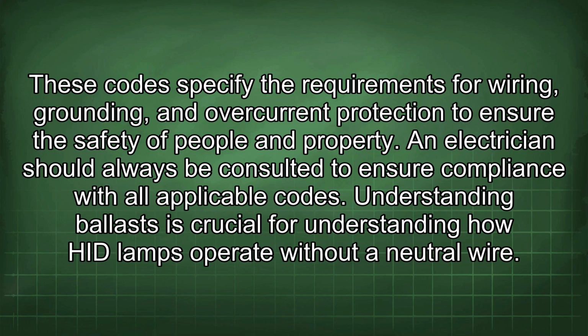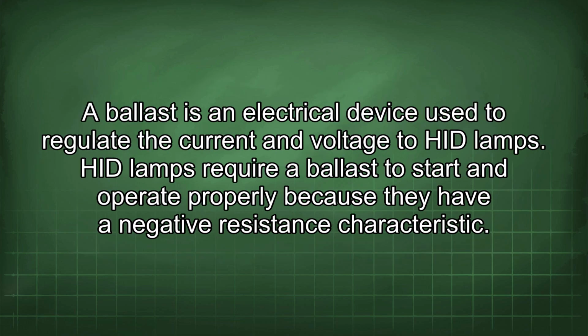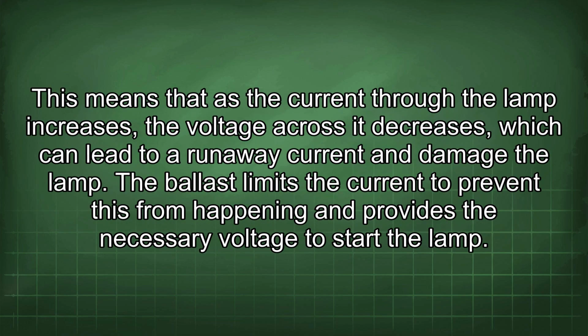Understanding ballast is crucial for understanding how HID lamps operate without the neutral wire. A ballast is an electrical device used to regulate the current and voltage to HID lamps. HID lamps require a ballast to start and operate properly because they have a negative resistance characteristic. This means that as the current through the lamp increases, the voltage across it decreases, which can lead to a runaway current and damage the lamp. The ballast limits the current to prevent this from happening and provides the necessary voltage to start the lamp.